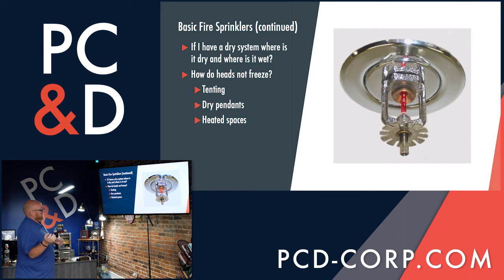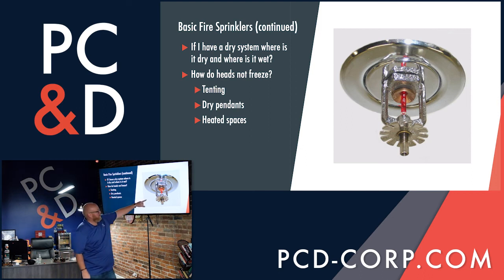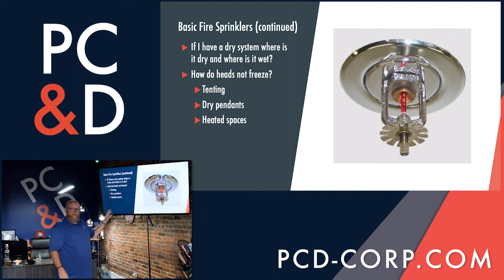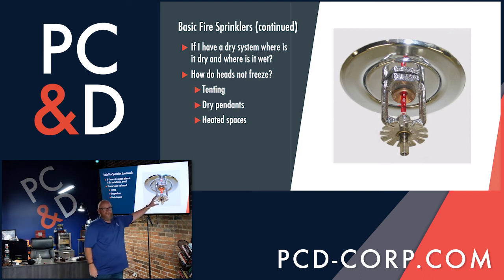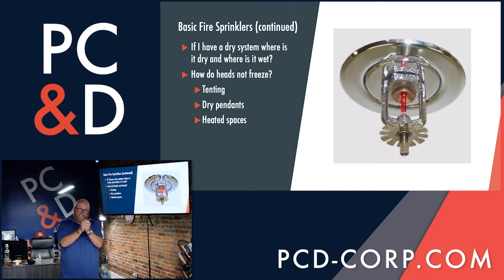So we talked briefly earlier about sprinkler heads, okay? So these, as you can see, are basic sprinklers. The heads for the most part are the same. We'll go over this one pretty quickly. This glass piece is literally holding back the water. It's holding back the water with this glass tube that has mercury in it, or a chemical that is heat sensitive. If you were to have a fire near a head like this, and the blaze was coming up near this head, as that chemical gets hot, that chemical expands.